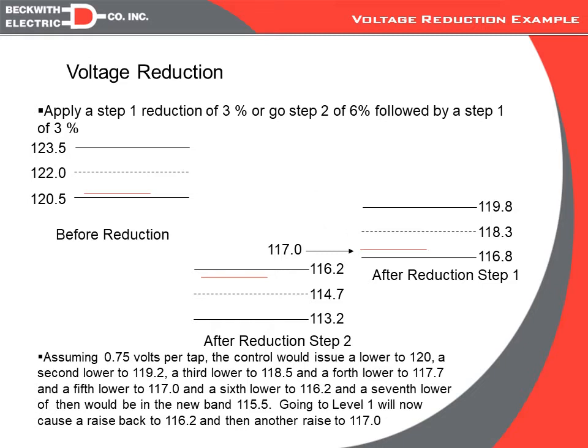But if we went to 1.5 volt bandwidth, then it would have had to take another tap to get into band. So the wider the bandwidth in normal modes is good because it reduces operations, but when you're in reduction, the wider bandwidth actually reduces the percentage that you're going to get, and therefore you may want to do one of two things. Either ask for a larger percentage than you need, knowing that you're not going to get everything you ask for, or you can send a command to reduce the bandwidth just prior to reduction, so that when you do go into reduction, the bandwidth will not be eating up as much.